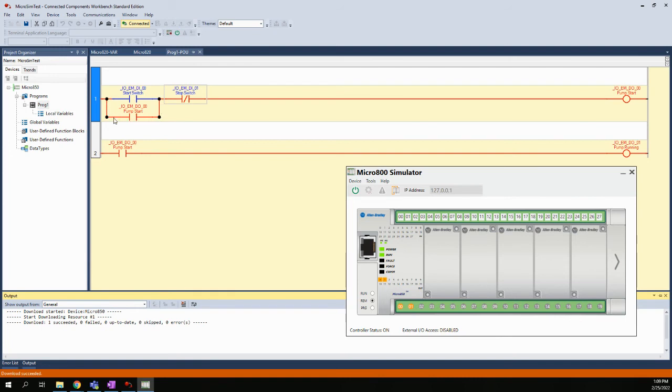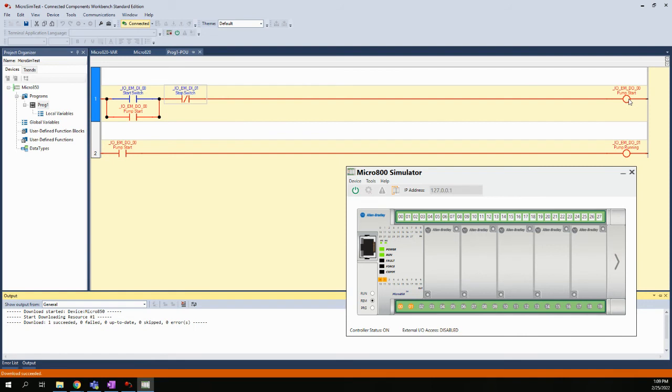I have my latched-in path around this switch or this push button using the pump start coil, so I still have a path through the stop button to the pump start. My two outputs stayed on even though I no longer had my input. The way we break this latch was to change the state of the stop switch, and that is tied to I/O EM DI 0-1.